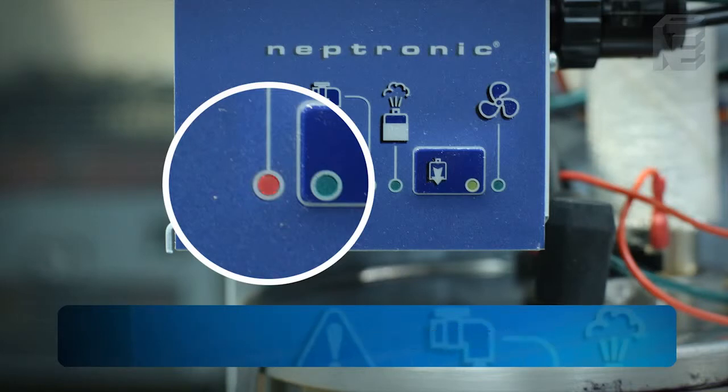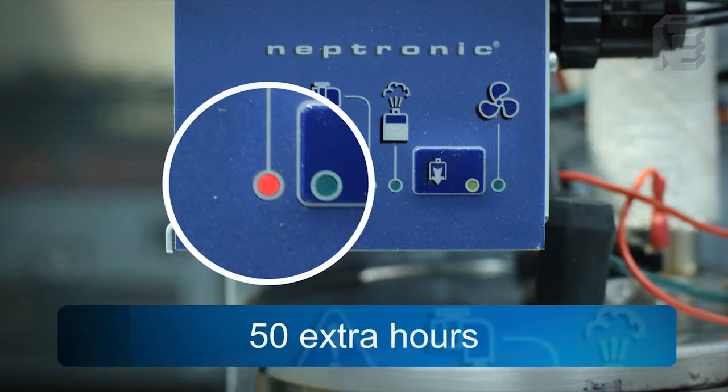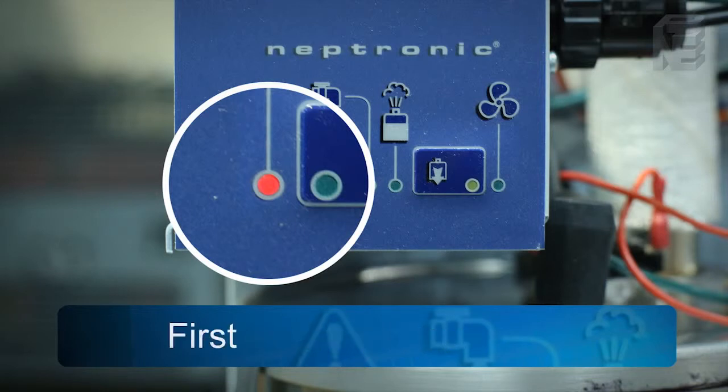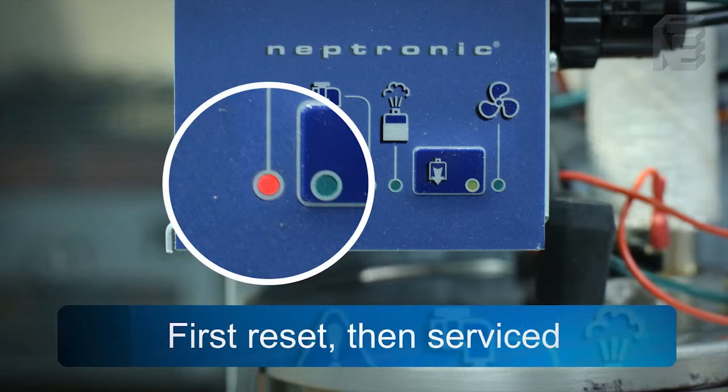The humidifier will operate for 50 extra hours with the red LED blinking continually. After the 50 hours have elapsed, the unit will automatically shut down and lock out, and the red LED will remain fully on. The humidifier must be first reset, then serviced.